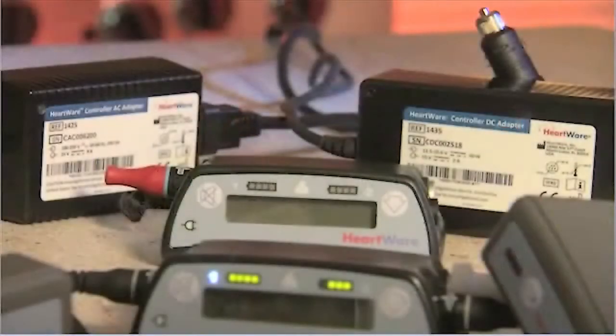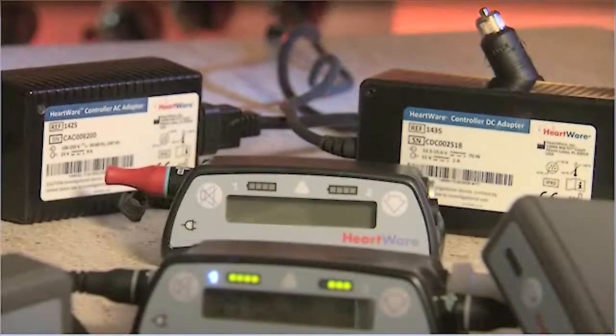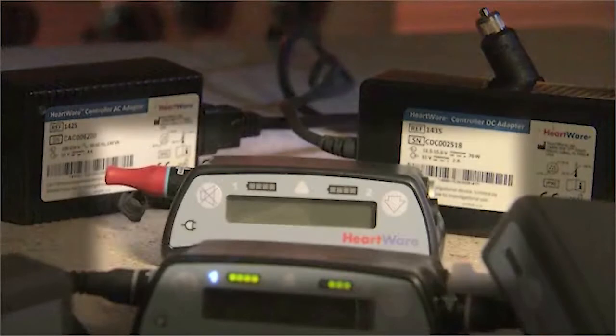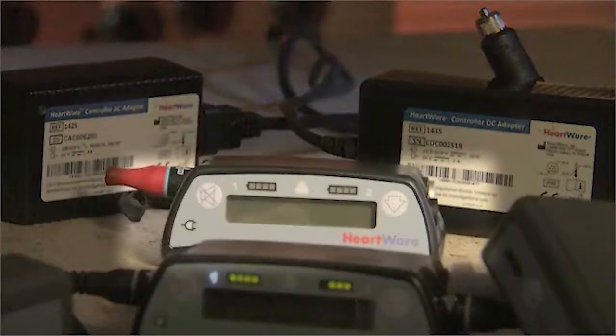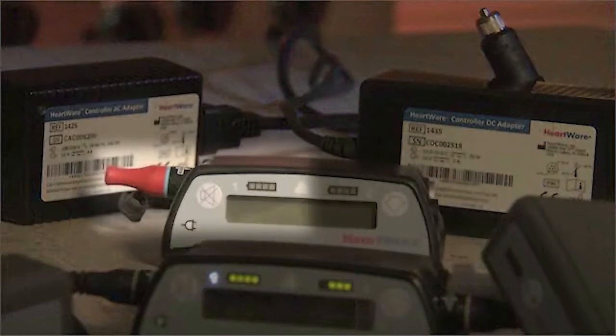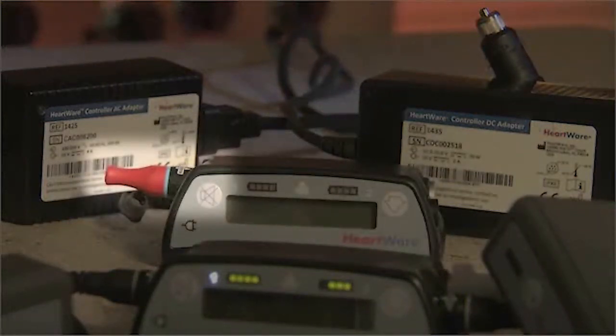A backup controller is included with the hardware system. The backup controller should be kept with the patient at all times, in the unlikely event there is a problem with the original controller. The backup controller will also hold the red alarm adapter. This is for emergency use only and is used to silence the no power alarm when power is removed from a controller that is no longer in use.